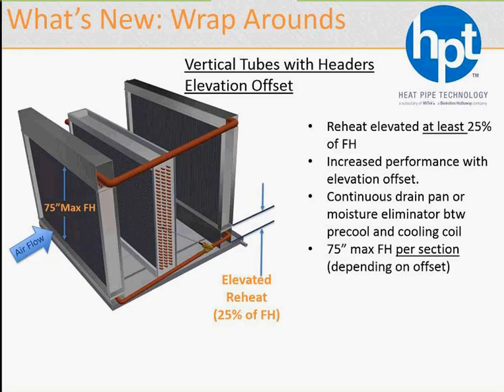Now the section height for this product, for this iteration, for this design, can go all the way to 75 inches. What does that mean? Fewer sections, so more area available for heat exchange and lower static pressure. And consequently, because of fewer sections, fewer circuits, fewer valves and controls, the price will be quite reasonable.